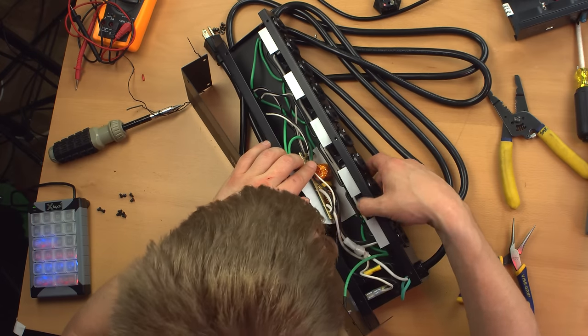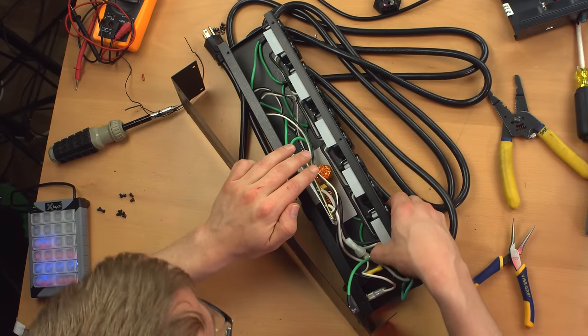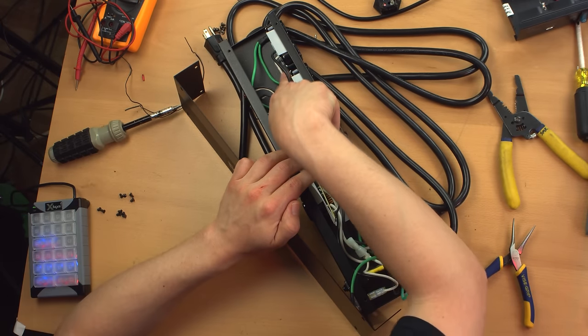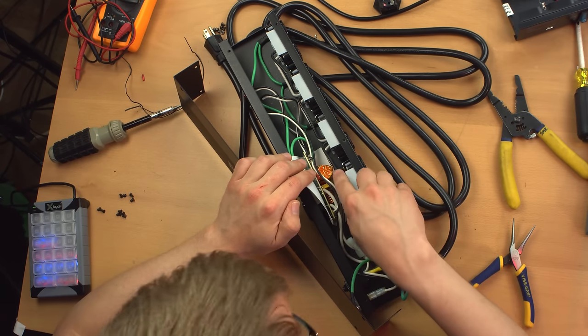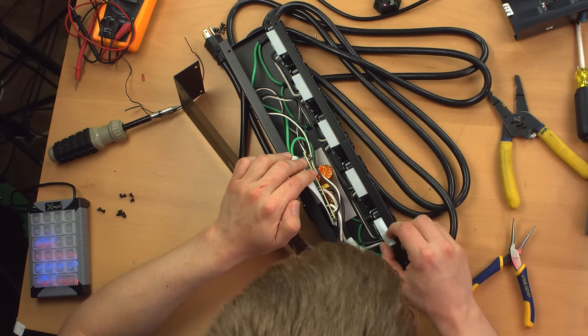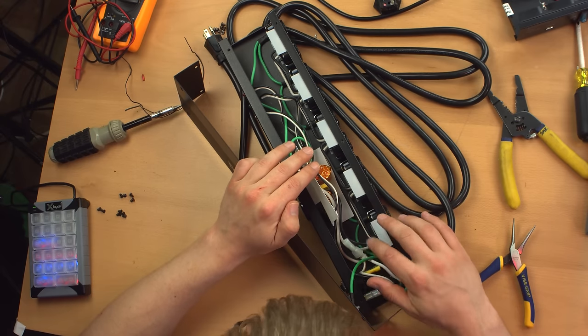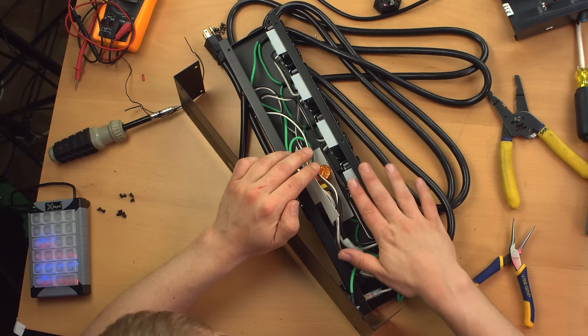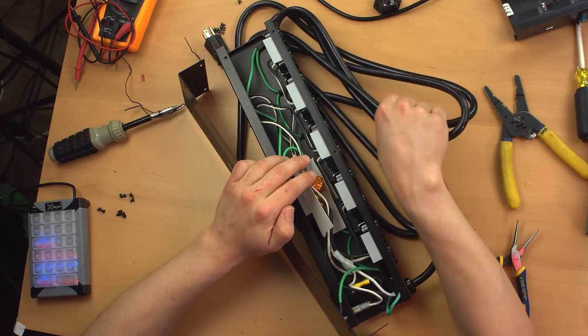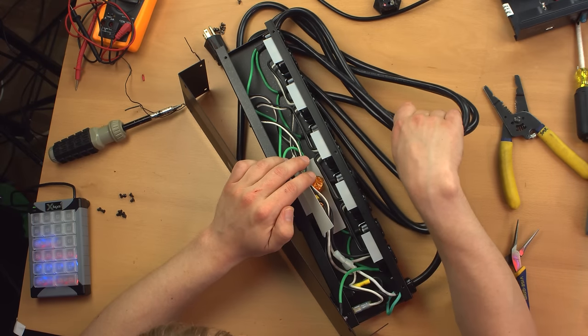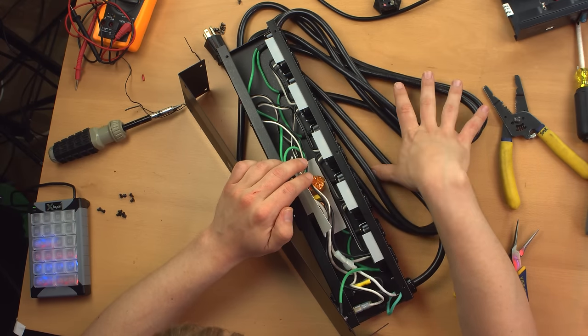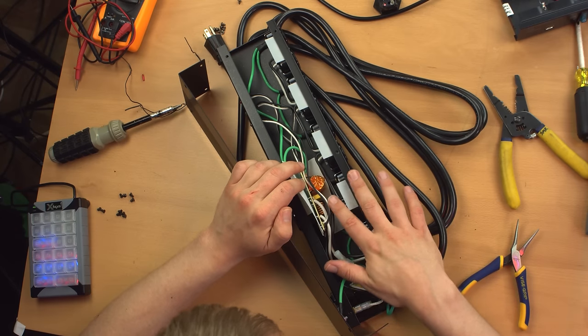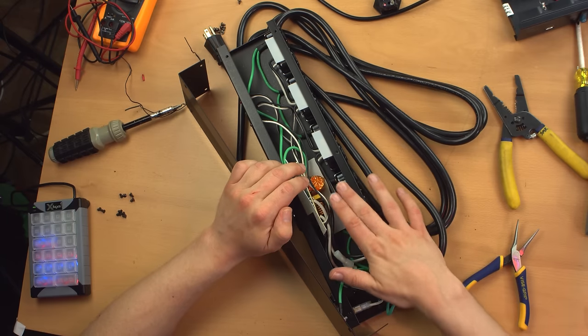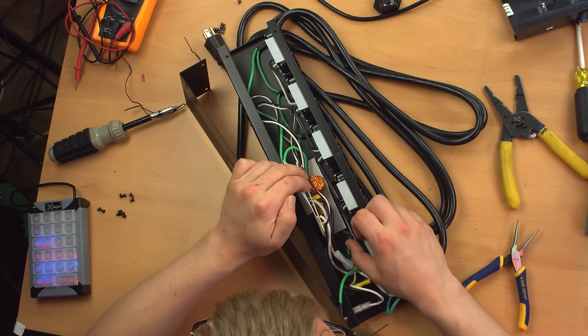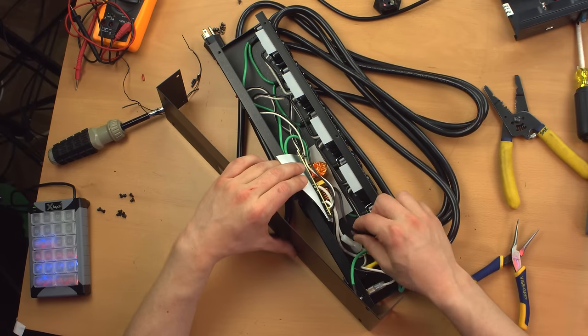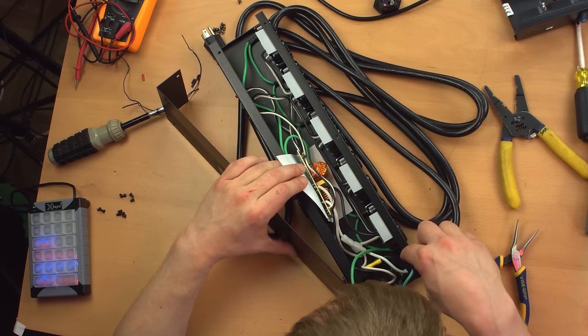Let me see if I can get an idea of the gauge on these interconnection wires. Let me just stick my, oh, 12 gauge, okay. This white one's clearly labeled as 12 gauge, and these black ones look to be the same size, so logically they're 12 gauge. Now 12 gauge is what you would expect to support a 20 amp load for building wiring and most any cord set. Actually, a cord set doesn't even need to be 12 gauge to be rated at 20 amps. So 12 gauge is actually overkill for this application, but I like to see overkill because heavier gauge is always a good thing, always better.